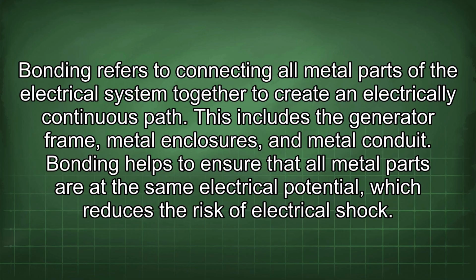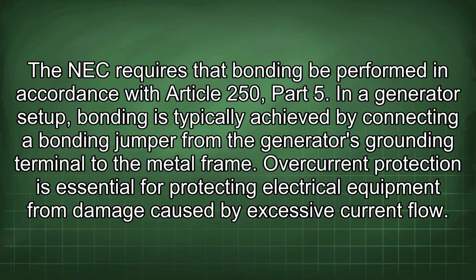This includes the generator frame, metal enclosures, and metal conduit. Bonding helps to ensure that all metal parts are at the same electrical potential, which reduces the risk of electrical shock. The NEC requires that bonding be performed in accordance with Article 250, Part 5. In a generator setup, bonding is typically achieved by connecting a bonding jumper from the generator's grounding terminal to the metal frame.